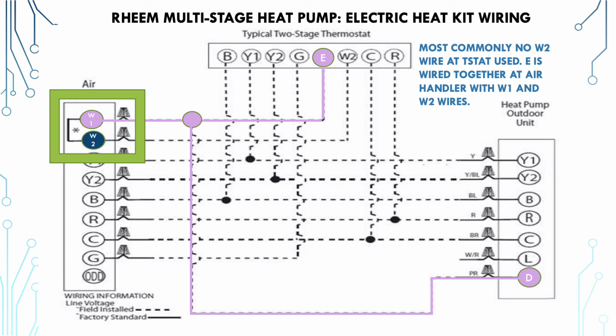Normally, you don't have a wire going from W2 at the thermostat down to the air handler. Normally, all of it's going to be jumpered. Now, this actual jumper at the air handler is not always pre-built in. It is just your wire nut. So you have E wire coming from your thermostat going to the electric heat W1 contact, and you're going to wire nut that together with the wire coming from the heat pump. Well, you just take that extra wire that's in the air handler for the other sequencer and you wire it into the same wire nut.